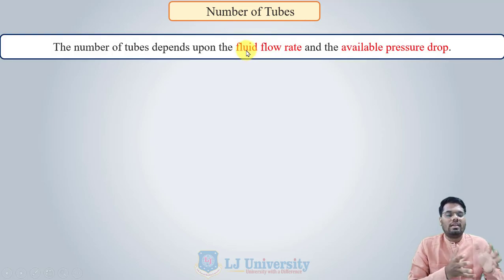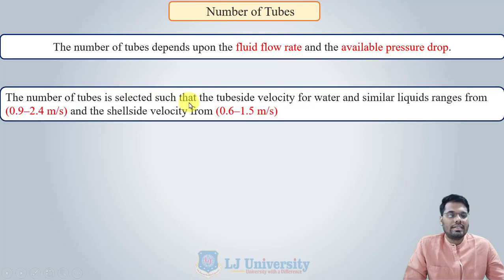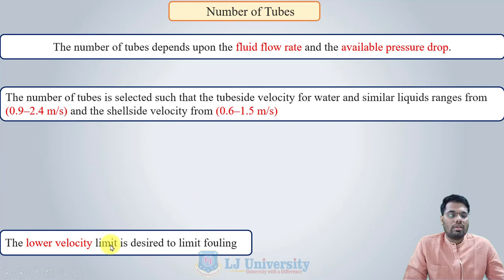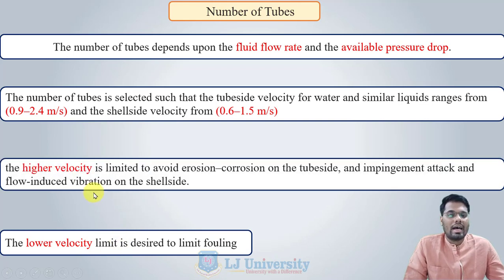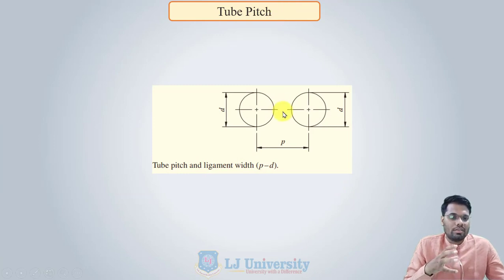The number of tubes depends upon the fluid flow rate and the available pressure drop. The number of tubes is selected such that the tube side velocity for water and similar liquids ranges from 0.9 to 2.4 m/s, and the shell side velocity varies from 0.6 to 1.5 m/s. The lower velocity limit is set to limit fouling, while the higher velocity limit is set to avoid erosion, corrosion on the tube side, and vibration.